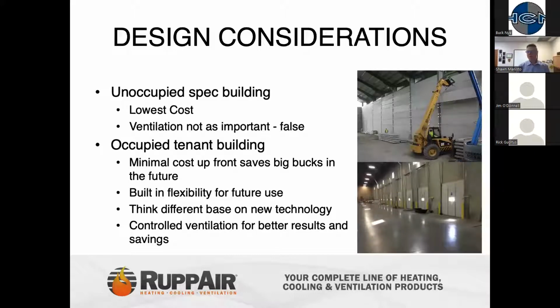So earlier on, we talked about those design considerations. One of the design considerations was understanding if it's going to be an unoccupied spec building or an occupied tenant building. So the biggest thing when we're working on these unoccupied spec buildings is that the mechanicals or the generals or the developers are mostly concerned about lowest cost. Lowest cost is what gets them to when a tenant's going to occupy.